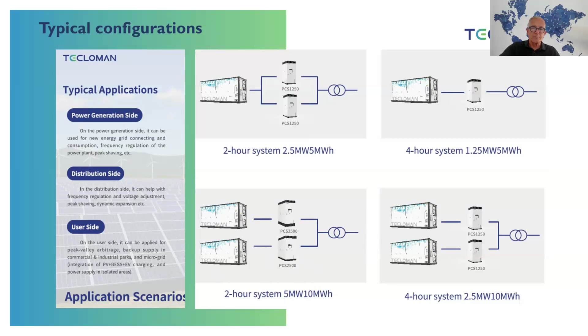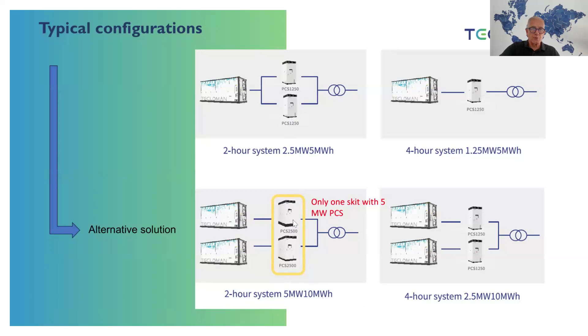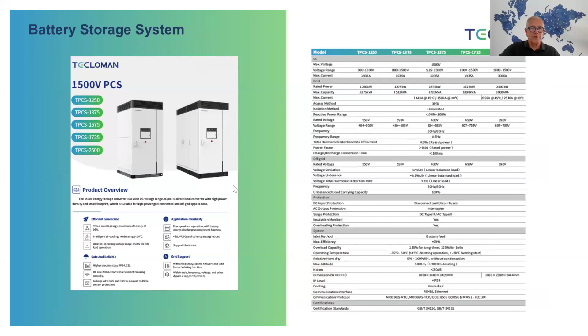So we have different kinds of opportunities, and Tecloman can deliver the whole structure and the whole system. You can have this as an alternative solution. For a 10 megawatt hour system, you can use two 20 feet containers, each 5 megawatt hours. You can use, as in this picture, two PCS systems, or you can use only one PCS system. It depends on what strategy the client is following. We are designing this with two PCS systems. In this case, if this is a 10 megawatt hour solution, each should be 2.5 megawatt. The PCS system from our side goes up to 3.5 megawatt each, if you want.